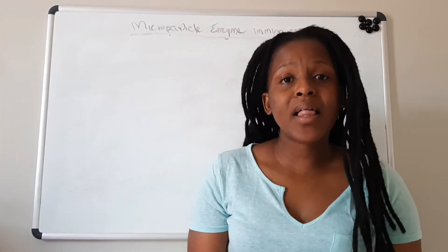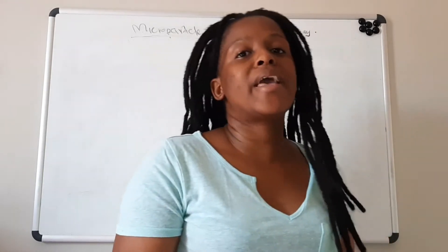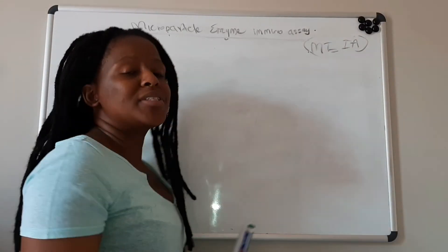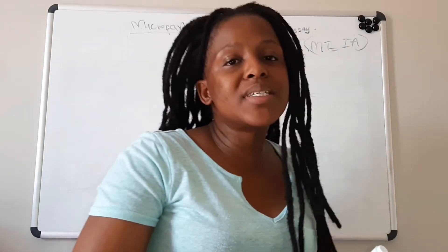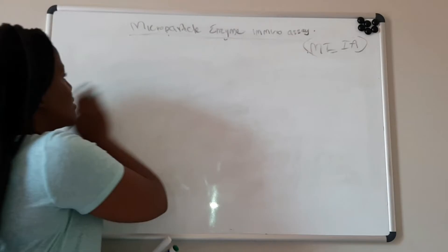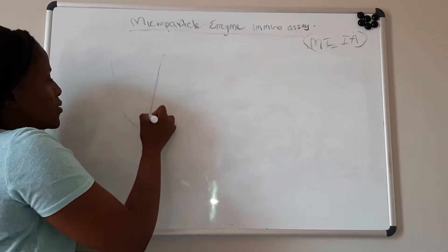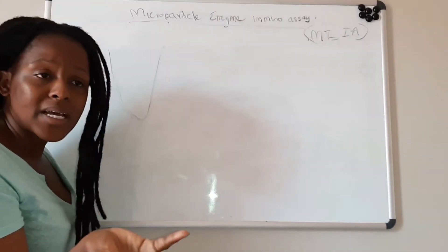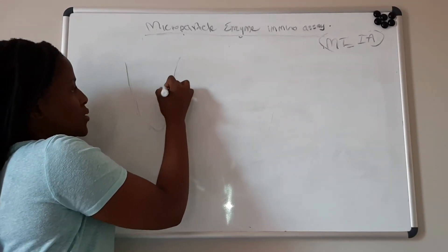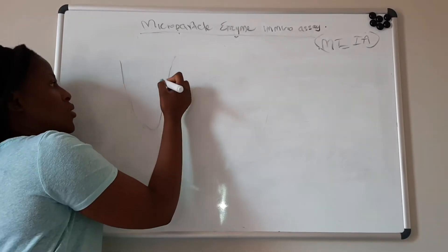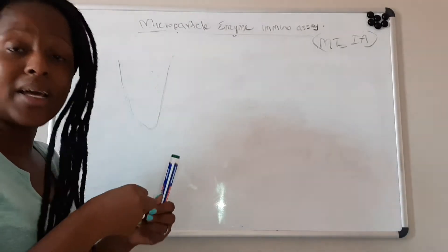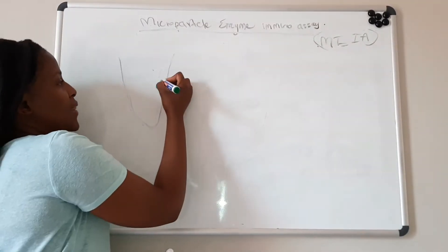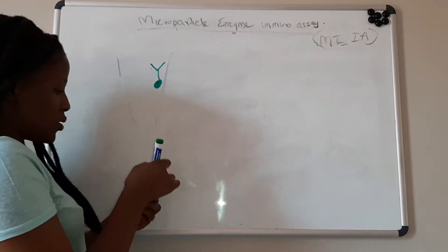Microparticle enzyme immunoassay, which can be abbreviated as MEIA. The principle of MEIA basically uses a solution of suspended latex particles — this will be your cuvette. So you're going to have a suspended latex particle, and this latex particle is attached to an antibody, which is suspended into the solution.